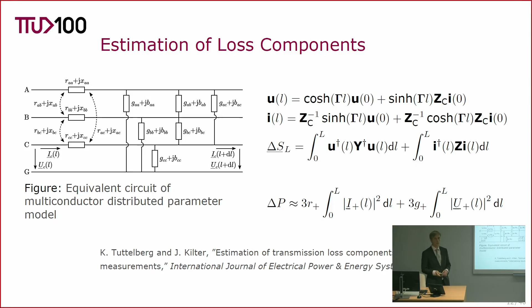So as I said, the main principle is that with PMUs, we can monitor the transmission line in more detail. We can obtain phasors measured at both ends of the transmission line from one time instance. And based on that and the transmission line model, we can derive components of transmission losses that correspond to Joule losses and corona losses.